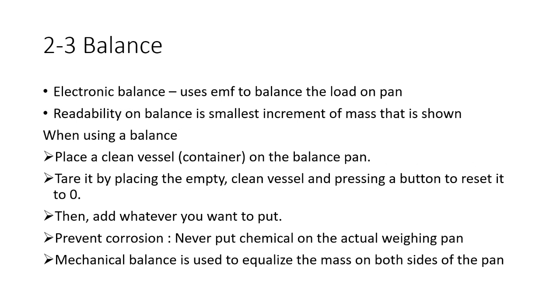Section 2.3 talks about balance. In electronic balance, it uses electromagnetic force to balance load on pan. The readability in balance is the smallest increment of mass shown in the balance. When using the balance, place a clean vessel (the container) on the balance pan.